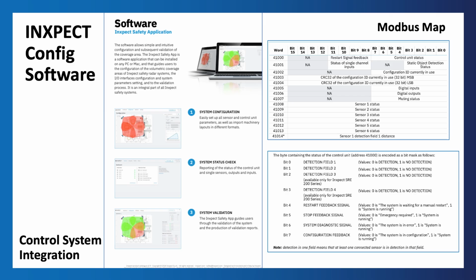Absolutely. Obviously the way these guys interface with the rest of the control system, at least in the case of the Horner OCS All-in-one Controller, is over Modbus. So what are the types of data that's being shared over Modbus with the system? Absolutely. We did 2 different scans in the Horner of 13 words each, I believe. The first 13 there being our general system outputs. So that's monitoring the entire system, all 6 sensors in series, and the controller status.